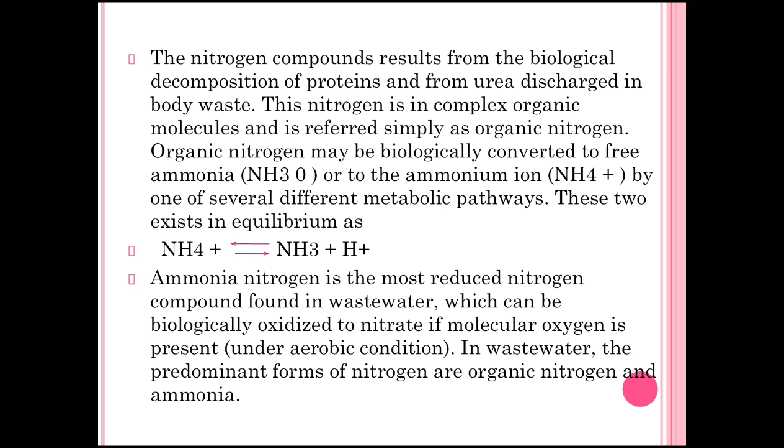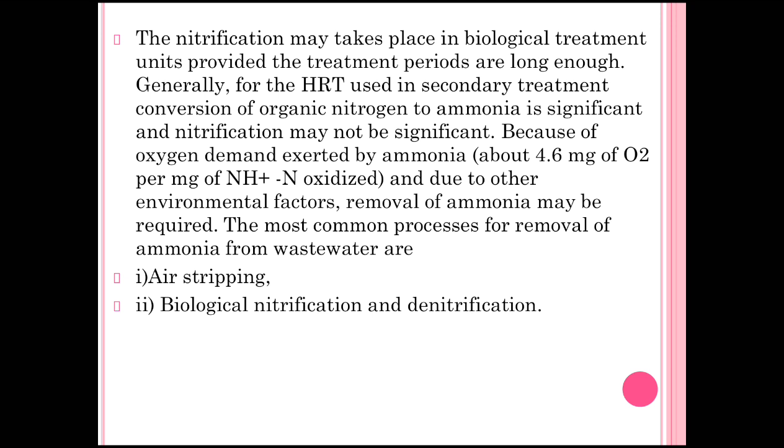In wastewater, the predominant forms of nitrogen are organic nitrogen and ammonia. These are the two main forms of nitrogen generally found. Nitrification may take place in a biological treatment unit provided the treatment period is long enough. For the HRT of secondary treatment, the conversion of organic nitrogen to ammonia is significant and nitrification may not be significant.